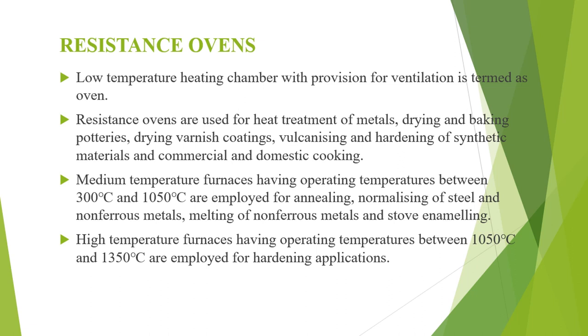Resistance ovens are used for heat treatment of metals, drying and baking potteries, drying varnish coatings, vulcanizing and hardening of synthetic materials, and in commercial and domestic cooking. Medium temperature furnaces have operating temperatures between 300 to 1050 degrees Celsius and are employed for annealing, normalizing of steel and non-ferrous metals, melting of non-ferrous metals and stove enamelling.